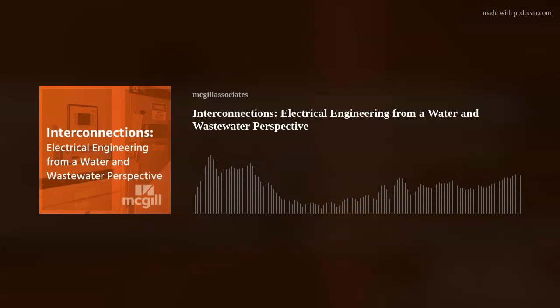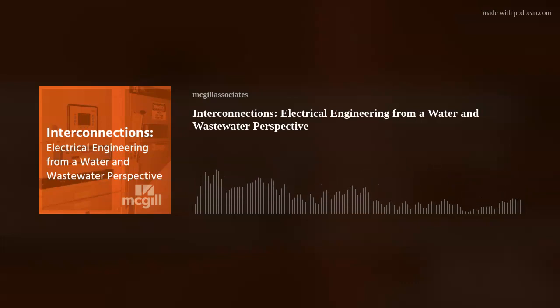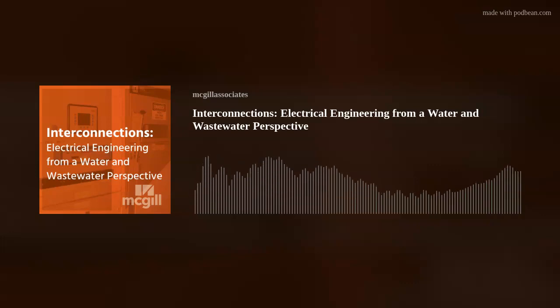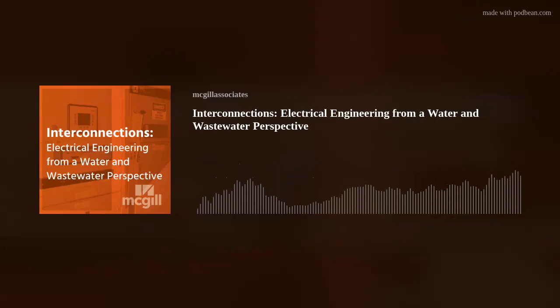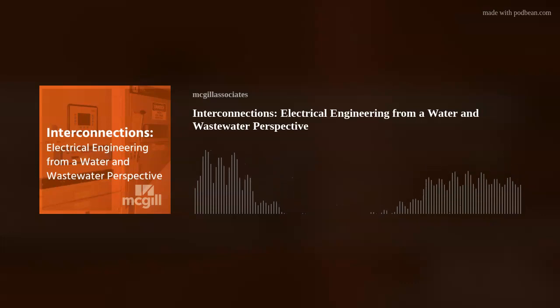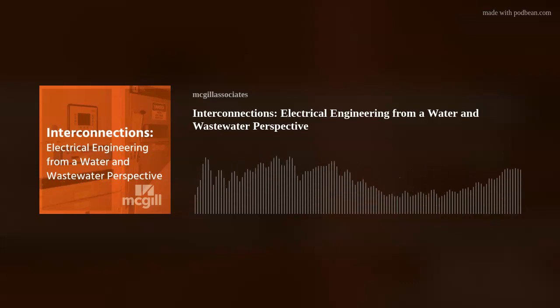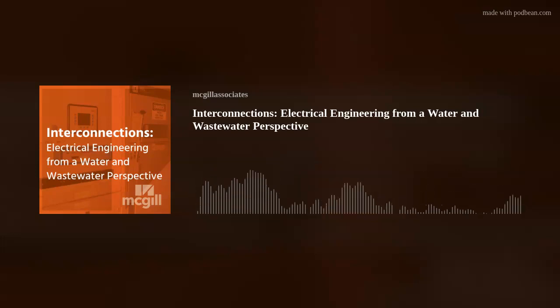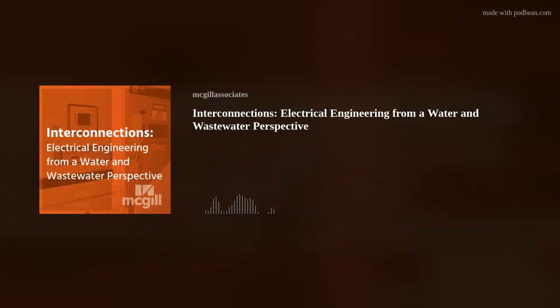From an engineer standpoint, these systems can be very simple or very complex behind the scenes, because they've got many inputs and outputs that have to be controlled, whether through a digital signal, an open and closed signal, or an analog signal that constantly monitors, say, the level in a wet well using an ultrasonic device. All that has to be brought back to the system and into that simple interface the operators see. There are various communication methods that can be used, whether Ethernet, fiber, wireless such as Wi-Fi, Bluetooth, radio system, or cellular. There's a variety of communication methods we look at to design a system, and a lot goes into the decisions we make working with a systems integrator and the client to make sure they're all happy at the end of the day.